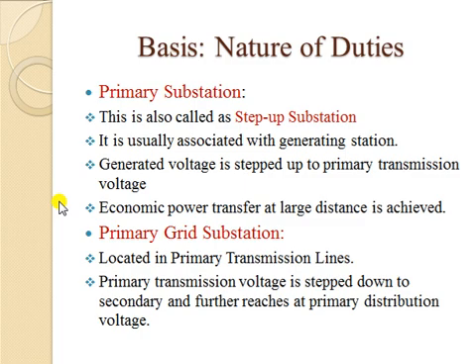The first is the primary substation, always present next to the generating station. The aim of this substation is to step up the voltage level. Power is generally generated at around 11 kV, 20 kV, 22 kV, or 33 kV. For economic power transfer, you aim for less current in the circuit because losses are I²R losses. For lesser current you need a higher voltage, so these are step-up substations associated with generating stations.